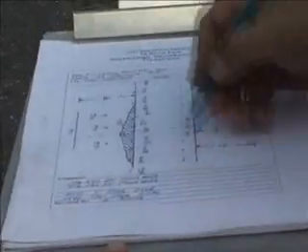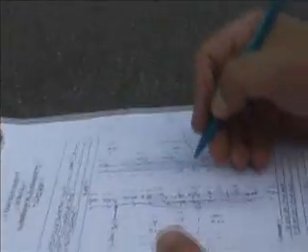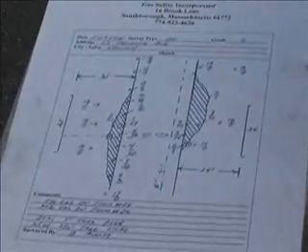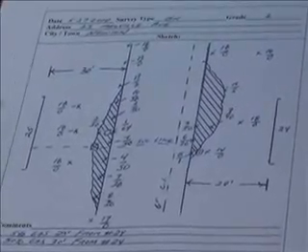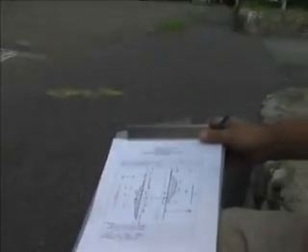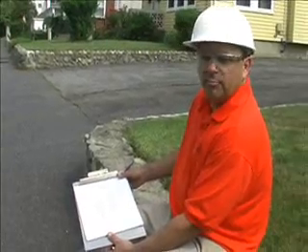And this is the 6-inch cast iron main, it's marked right here, 6-inch CI. And here is the service line. So looking right here, you can see that there's gas going up here. This reading right here was 23 feet. And this is a continuously paved area over here. A leak that really should be fixed, not only to save these trees, but for safety reasons. And this is Melville Ave, and I'll put that right in here. So there you have a properly documented gas leak affecting trees, and checking for safety.